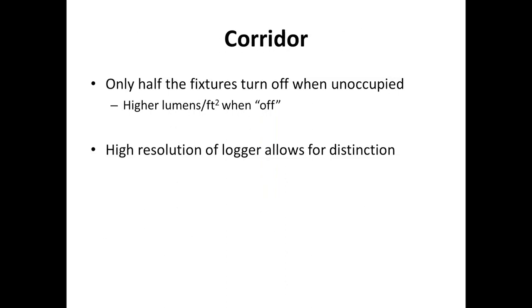This led us to assume that light fixtures were not turned off fully when unoccupied, that a lot of the building lighting was still remaining on, and that there was significant light coming in from other sources, so we may not have needed as many lights to be on. The occupancy sensors and the daylighting sensors in that space could be adjusted to turn off the fixtures more based on ambient light.